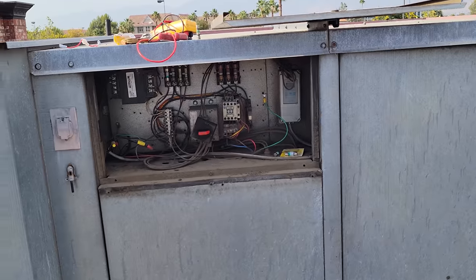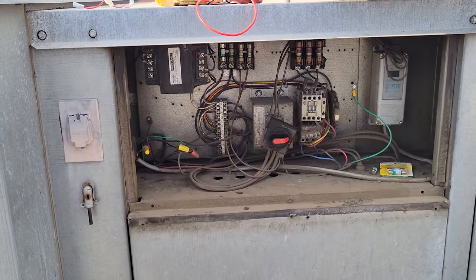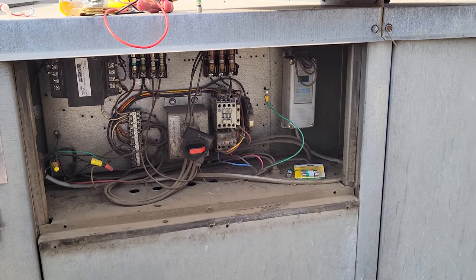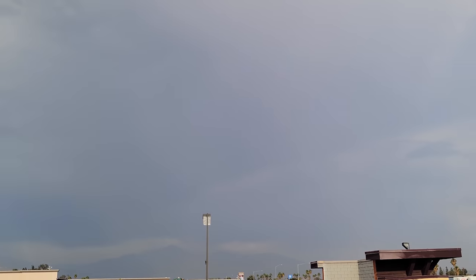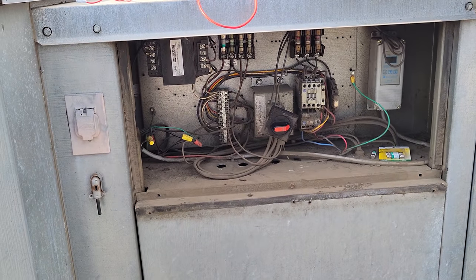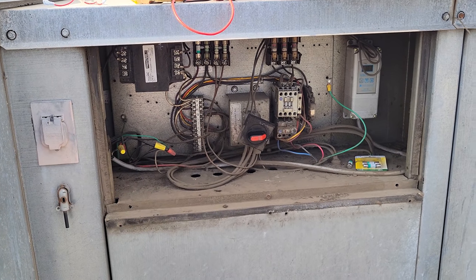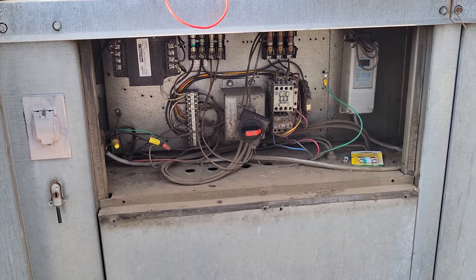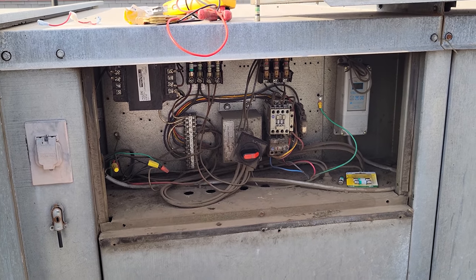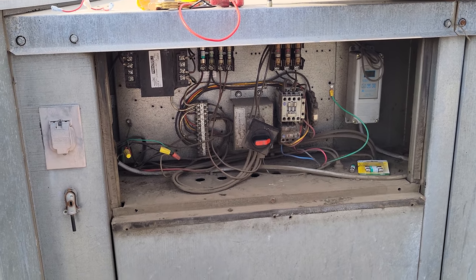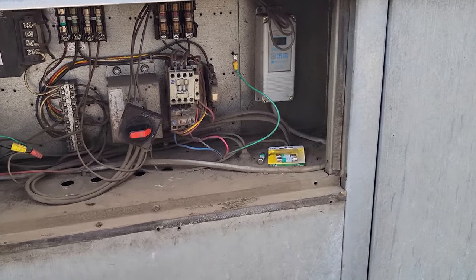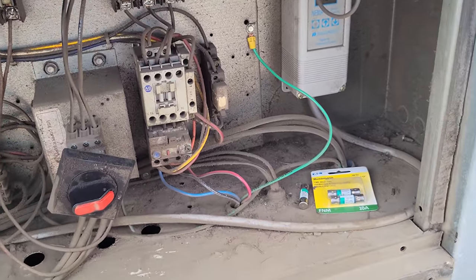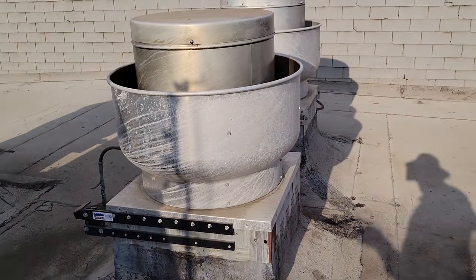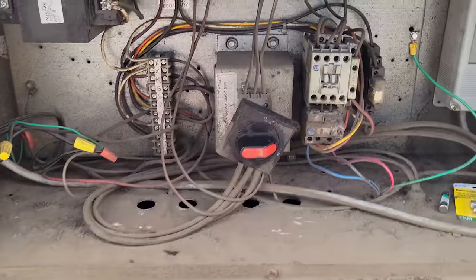So because we lost that control voltage, they lost the entire system. What caused it to blow? You know, we got thunderstorms right there. We got lightning today. They did have what they call a power surge. They said the lights flickered like two or three times and then everything went down right after that. When I pulled up to the building, the stoplights were flashing like they lost power. So something happened. I would hope that's what blew the fuse. I don't know though, and they're already cooking. They've already got equipment in there, so I can't play with it. I can't, you know, tinker with it.